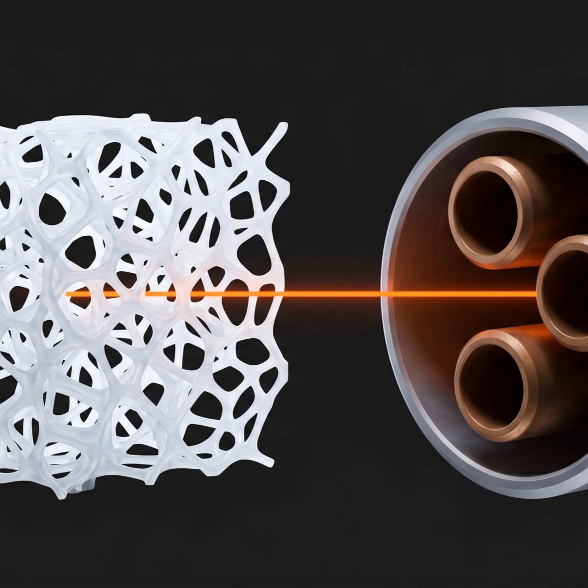The core piece of technology is a clamp-on ultrasonic flow meter, which is a brilliant piece of engineering on its own. You don't have to shut down the chiller or cut into the heavy gauge copper. The meter clamps onto the outside of the discharge line and uses acoustic signals to measure the velocity of the liquid or gas flowing inside the pipe.